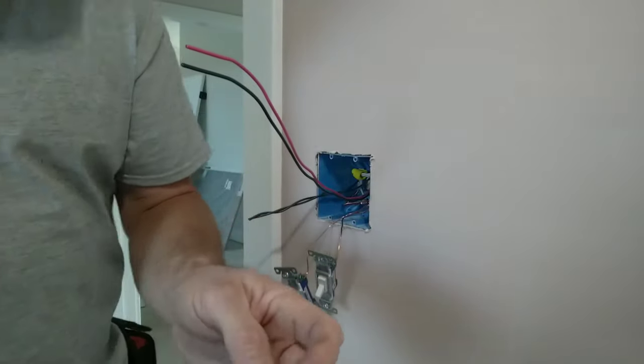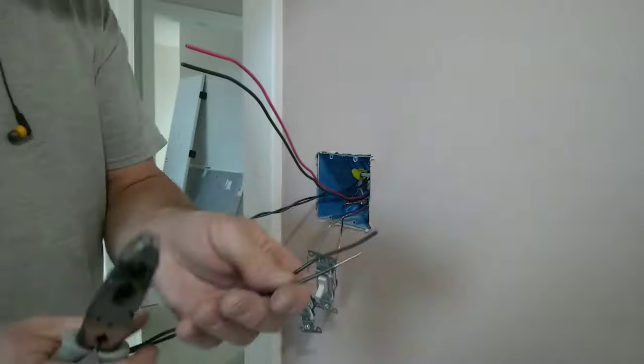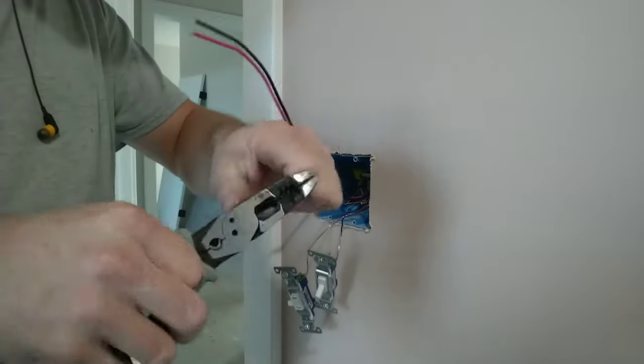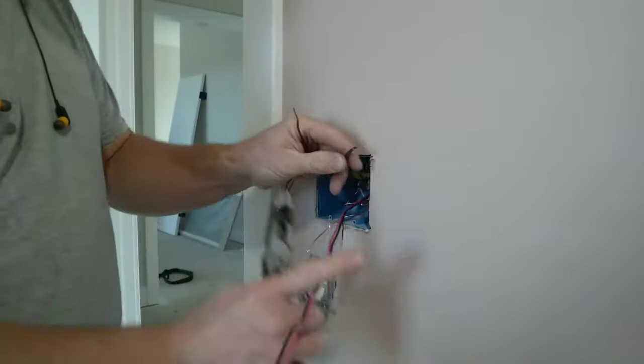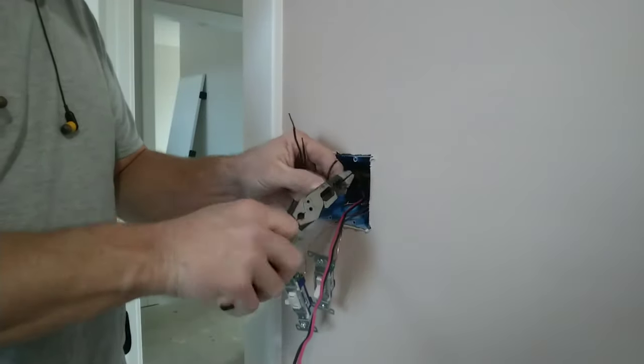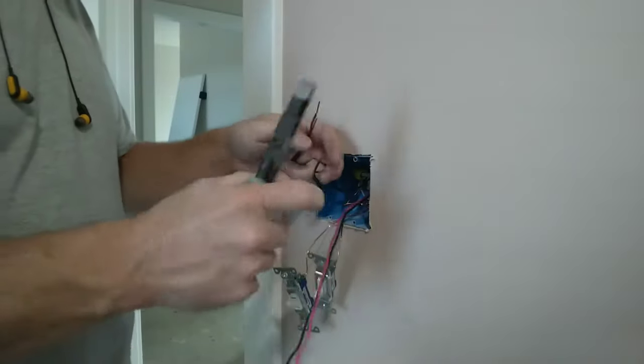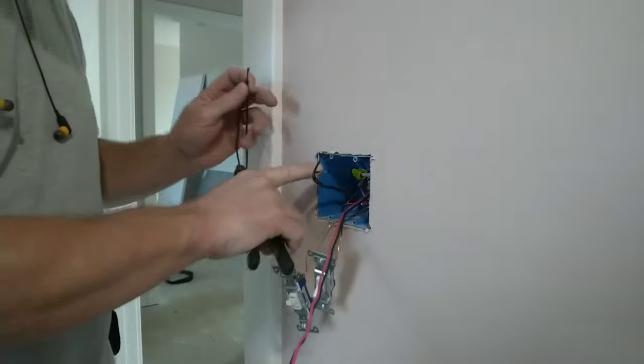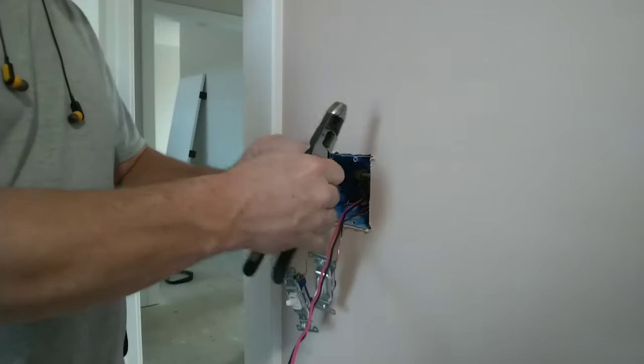One of these pigtails I can use. That one's a little too short for my taste. So I got another pigtail here. I'm gonna strip 7/8 of an inch off of it. Now that these two wires are cut and lined up, I'm gonna strip 7/8 of an inch on those. Now we're gonna take all four of these. These are pre-twisted, lightly twisted. We're gonna group all four of these together.